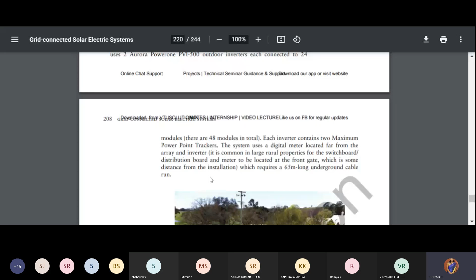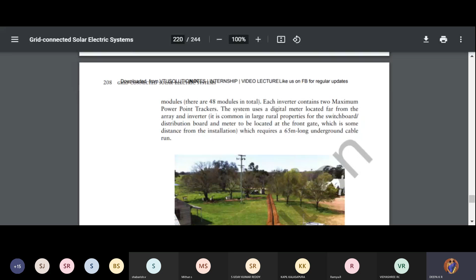They say it is common in large rural properties for the switchboard or distribution board and the meter to be located at the front gate, which is some distance from the installation. It is a common strategy in rural areas, and it was completed like this. You can see the picture. This is the rural area, as I said. Normally the switchboard, because you need to see the values you're generating and how much it is distributing, is kept at the front gate. So the distance will be a little far from the installed PV system as well as the inverter.